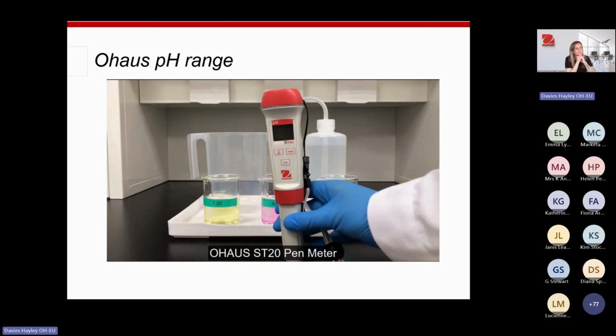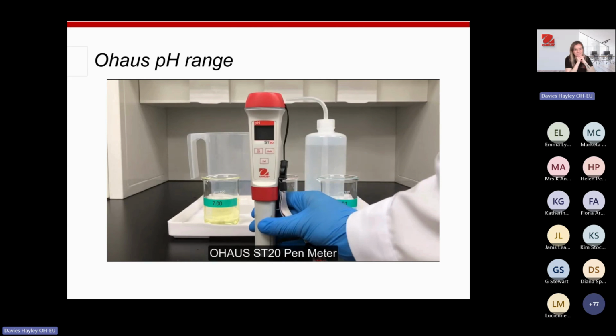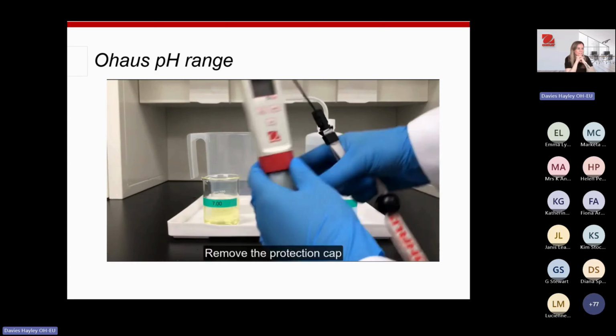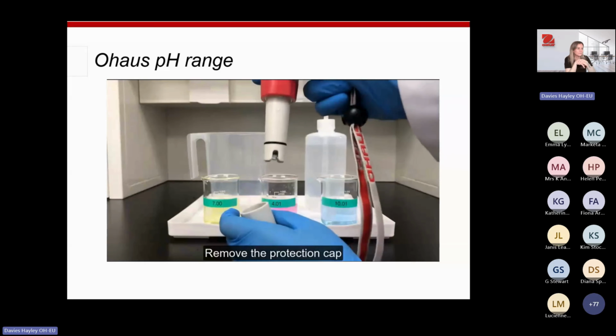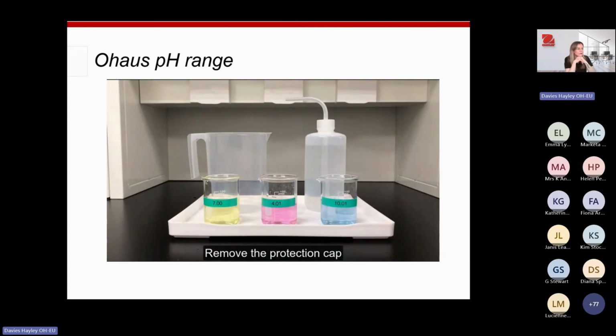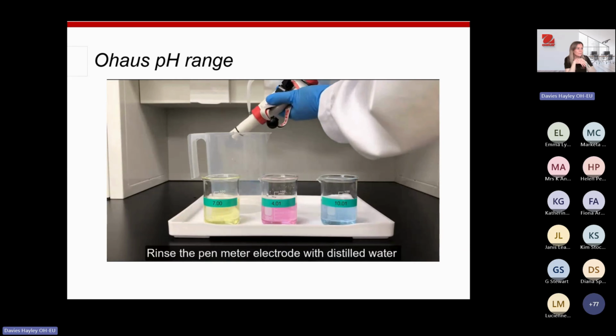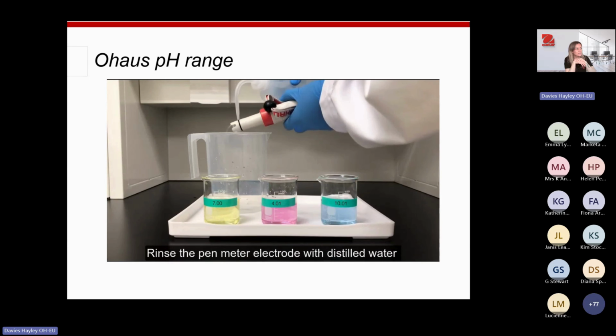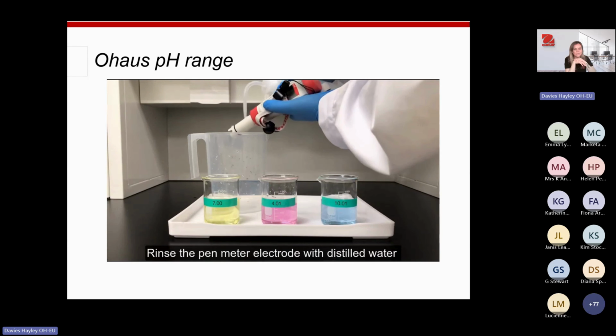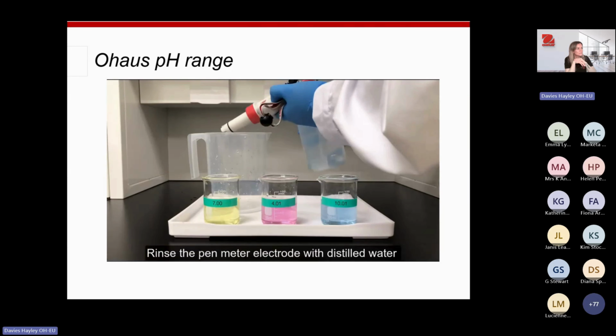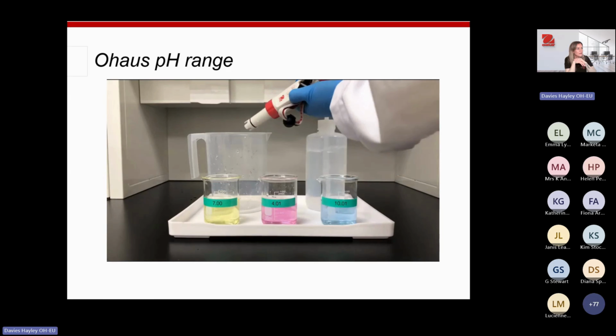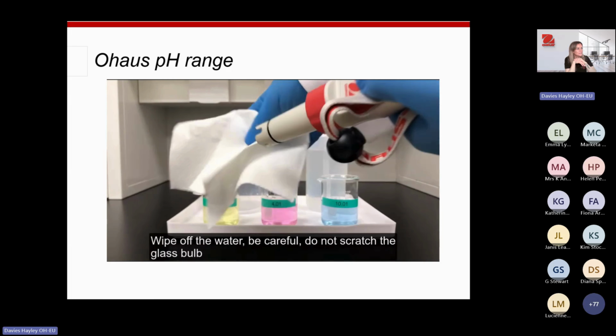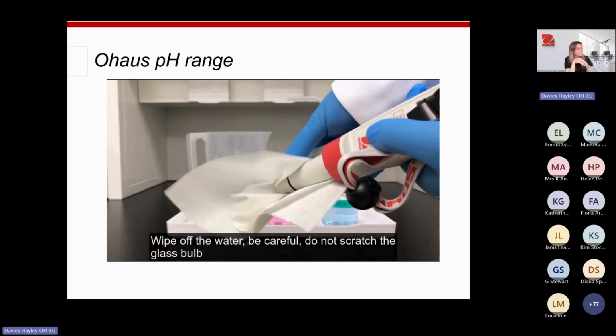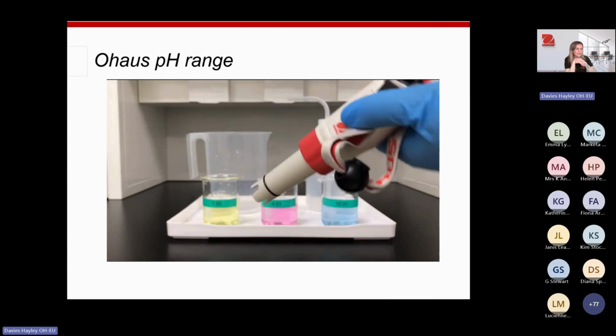So this is the ST20, and this is going to show you how you can calibrate the ST20 pen meter. As you can see, we've got our pH buffers already there. We will remove the protection cap, and we've got distilled water, and we're just going to give it a rinse. So this is all you need to do to clean them. Rinse it with distilled water, and then gently just dab the end with a paper towel.